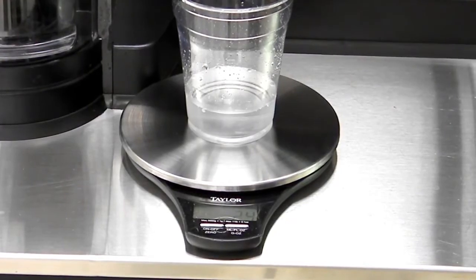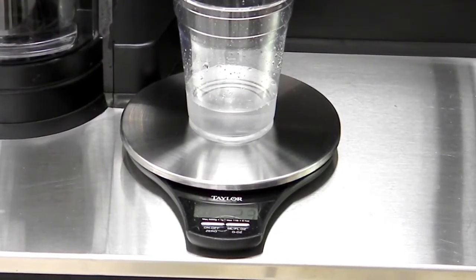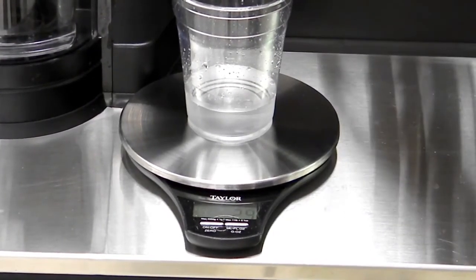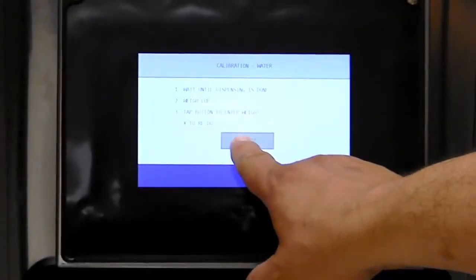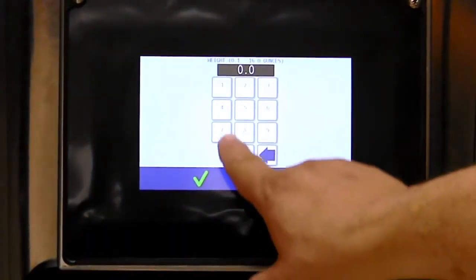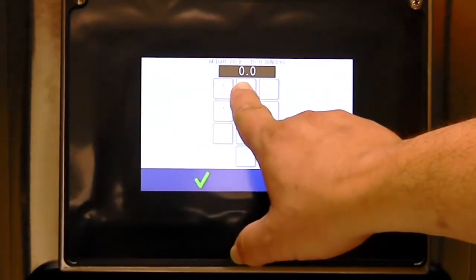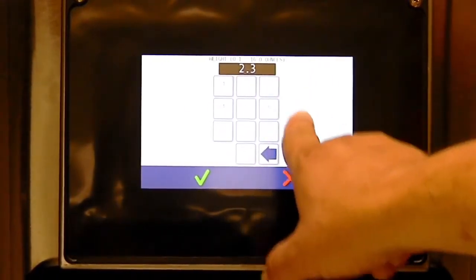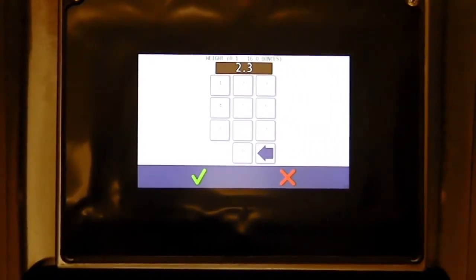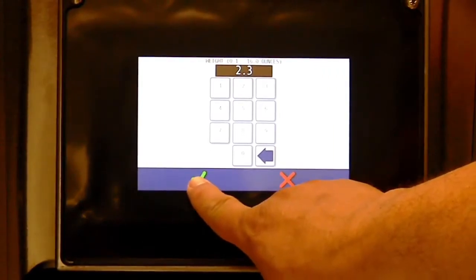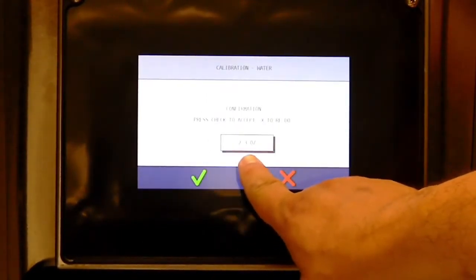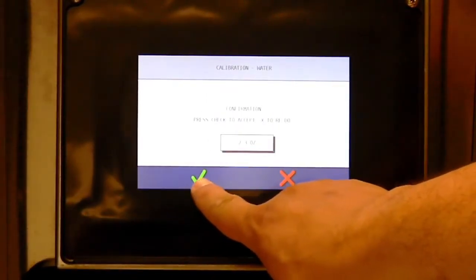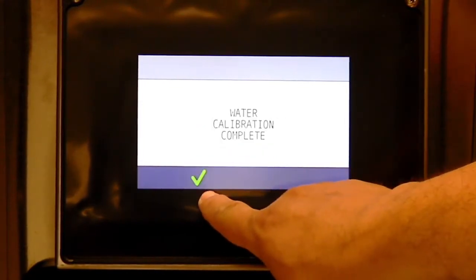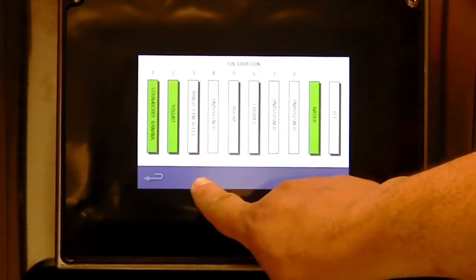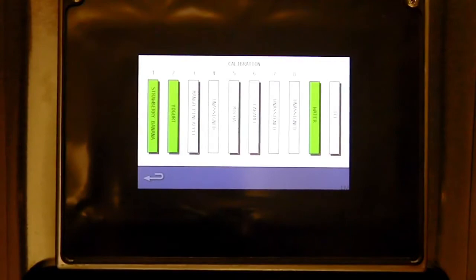It's bouncing back and forth, 2.3 to 2.4 ounces. We're going to touch our box on the screen. We're entering the weight. The scale has kind of stopped bouncing at 2.3 ounces, so we'll enter 2.3. We'll hit the check mark. Confirm that the machine did accept what we entered. Again, hit the check mark. Water calibration complete. Now we'll go back and run through the water calibration again.